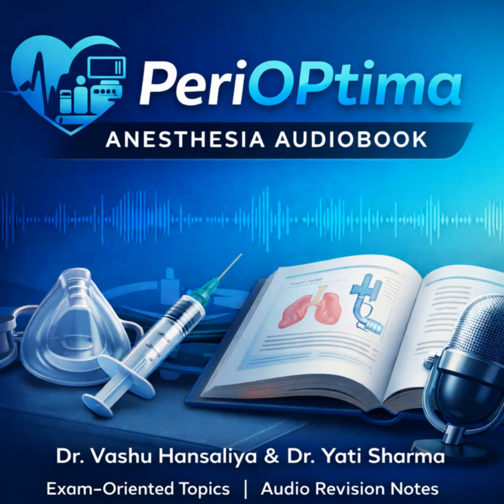Yeah. What else? Arrhythmias, especially something like atrial fibrillation. The device relies on a regular, predictable cardiac cycle to average its readings. An irregular heartbeat throws the whole algorithm off. And what about in the operating theater? Surgical interference. That's a huge issue. If the surgeon is using diathermy or electrocautery, that creates a massive electrical storm in the patient. The impedance monitor just goes haywire. It's completely unusable during active cautery.